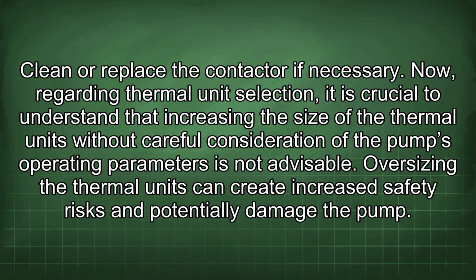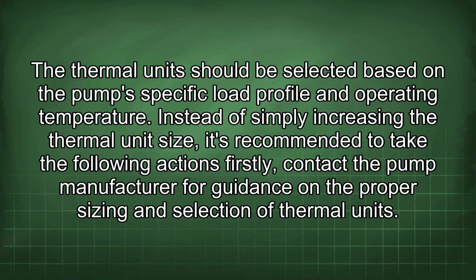Now, regarding thermal unit selection, it is crucial to understand that increasing the size of the thermal units without careful consideration of the pump's operating parameters is not advisable. Oversizing the thermal units can create increased safety risks and potentially damage the pump. The thermal unit should be selected based on the pump's specific load profile and operating temperature. Instead of simply increasing the thermal unit size, it's recommended to take the following actions.